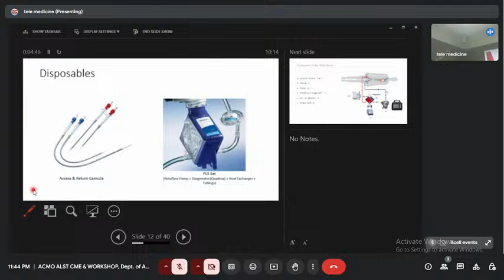So, just to summarize what I have told, your blood is drained and through the pump gets into the oxygenator, and inside the oxygenator the gases come, oxygen enters and the CO2 gets washed out, with the oxygen blender on the extreme side on that number 5. This is just similar to what you have on your pump or on your anesthesia workstation, right? And after the blood gets oxygenated, it gets returned to your preferred site, whether it's a VA ECMO or VV ECMO or the different types we'll discuss.